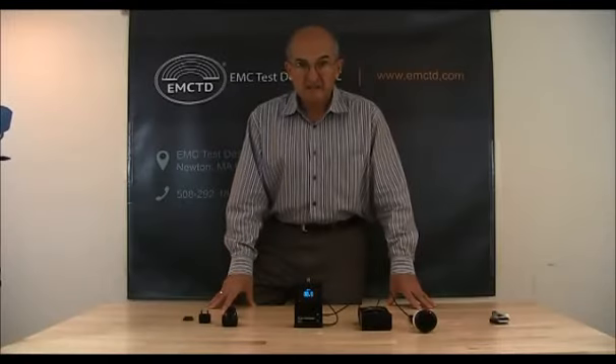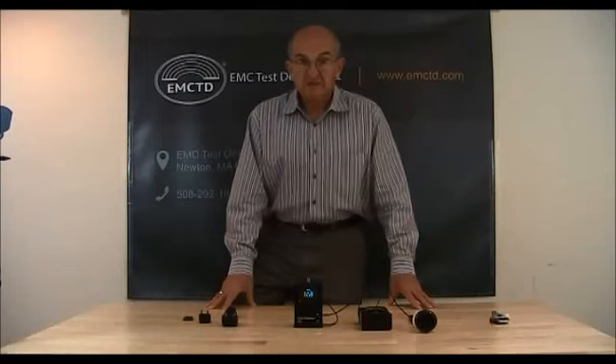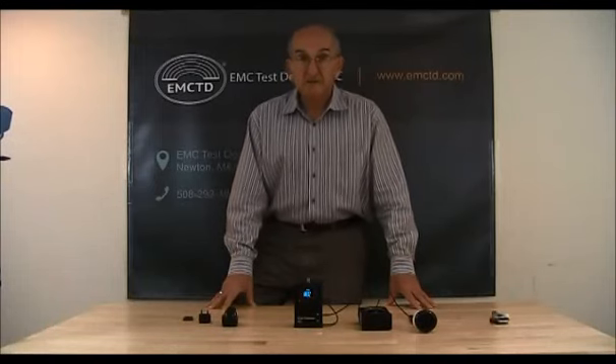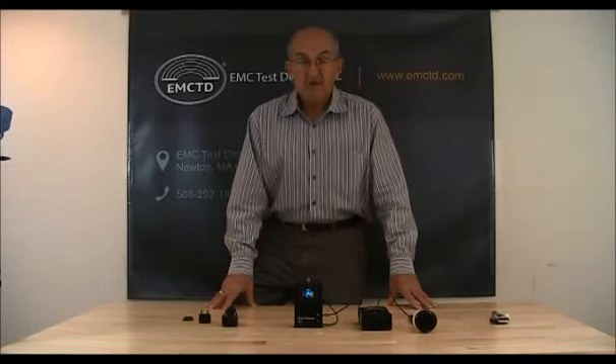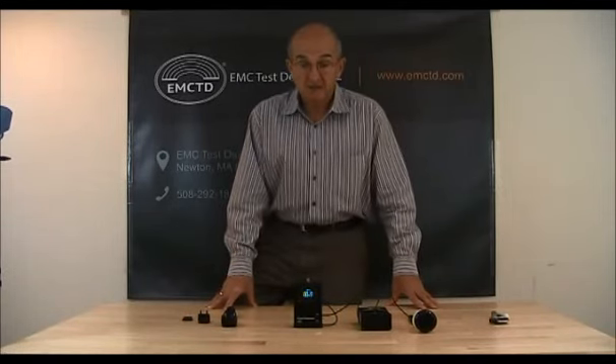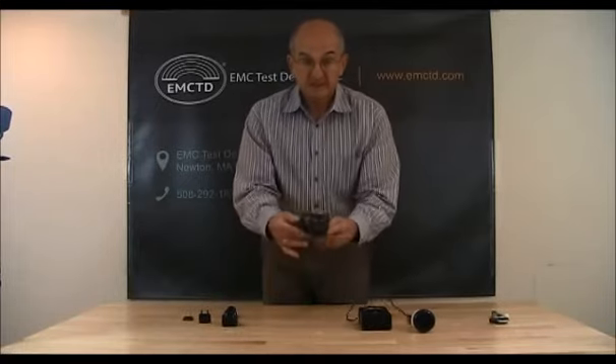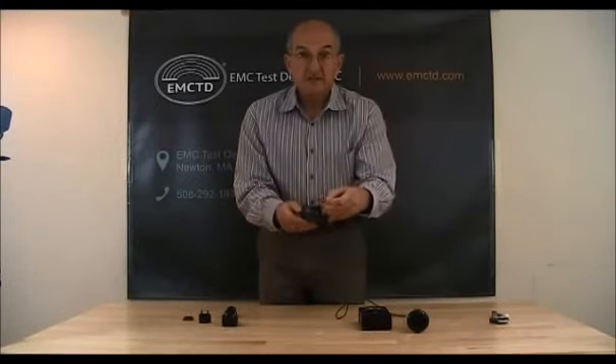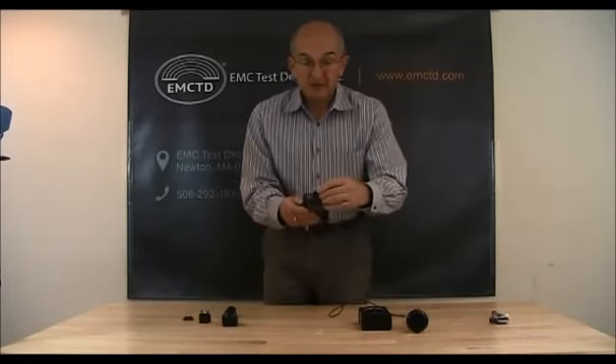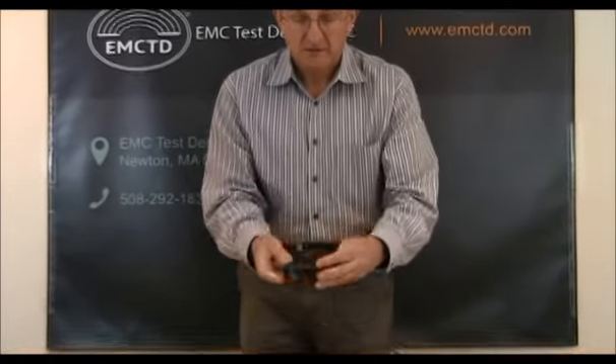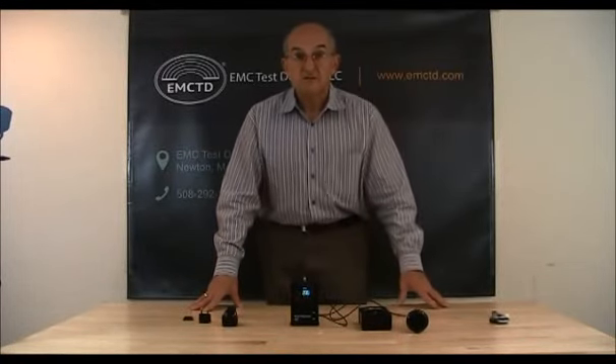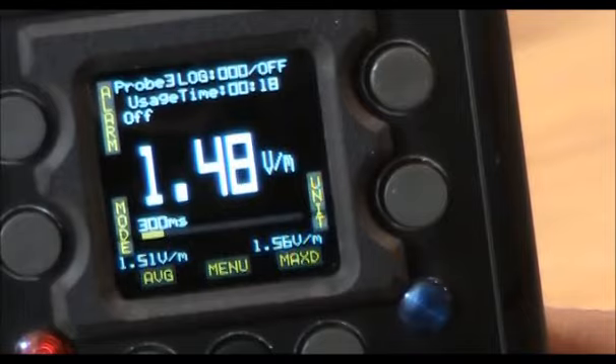Second important thing is that this meter allows you to see data in both field units and power units. This is very important sometimes for microwave measurement. Another very important feature of this meter is it has unique logging capabilities. Because this meter is supplied with SD card, this SD card can be up to 2 gig of memory, and you can log tens of thousands of data points, and you could have up to 1000 different files logged into this meter.